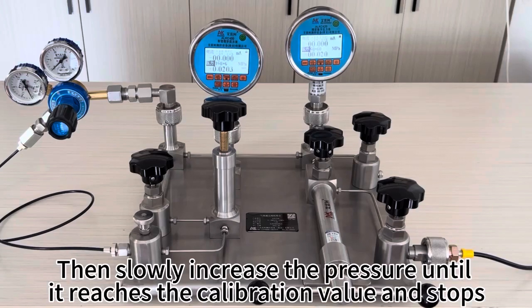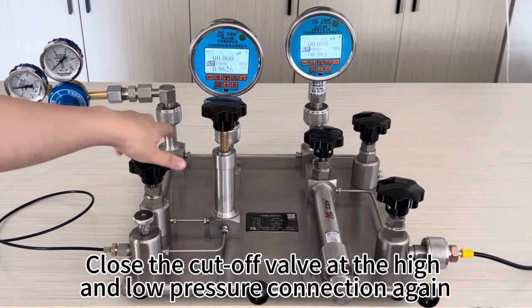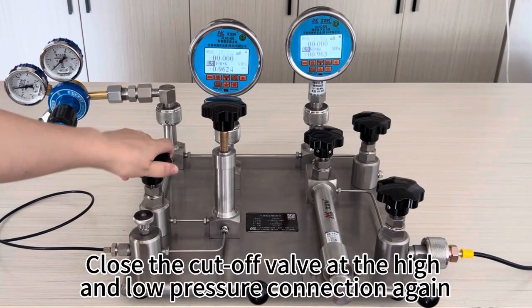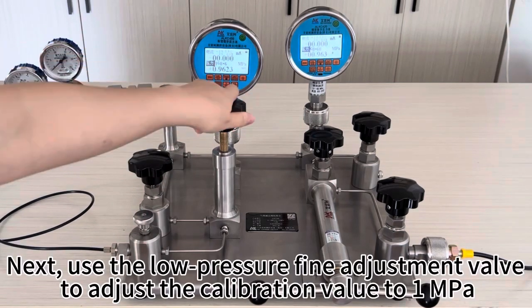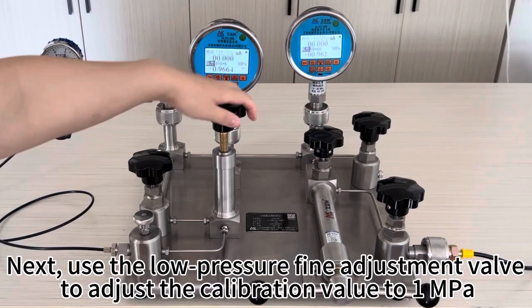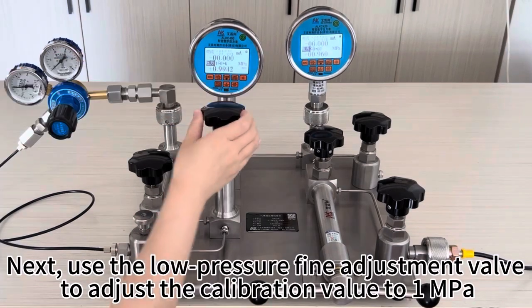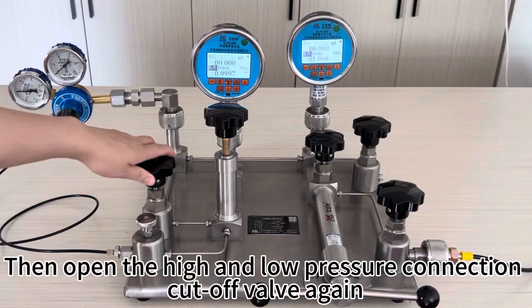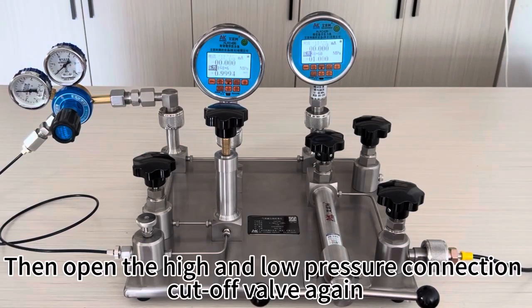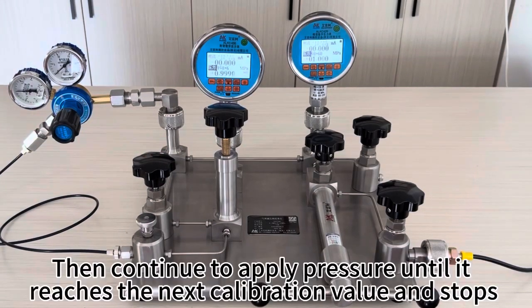Then slowly increase the pressure until it reaches the calibration value and stops. Close the cut-off valve at the high and low pressure connection again. Next, use the low-pressure fine adjustment valve to adjust the calibration value to 1 MPa. Then open the high and low pressure connection cut-off valve again. Then continue to apply pressure until it reaches the next calibration value and stops.